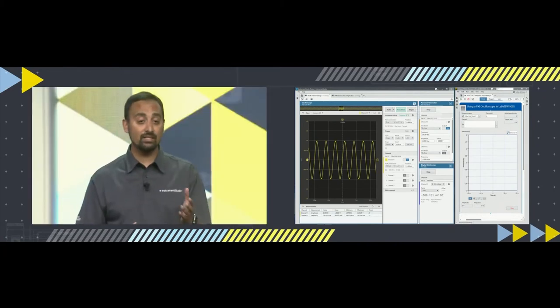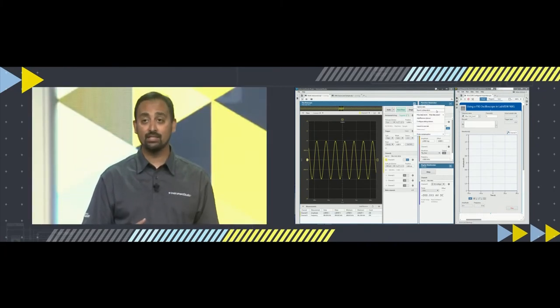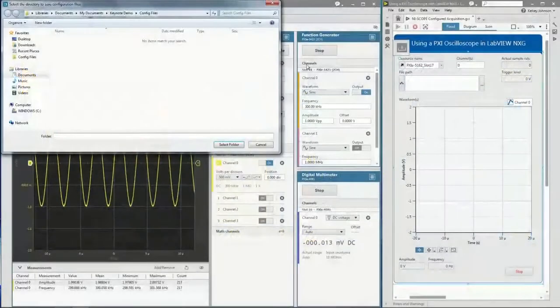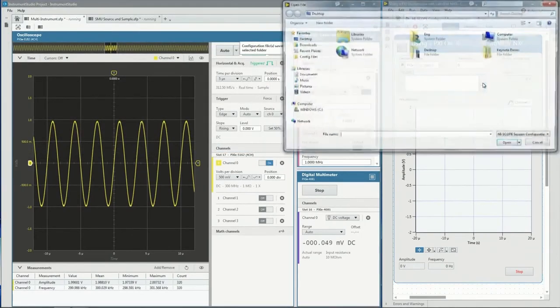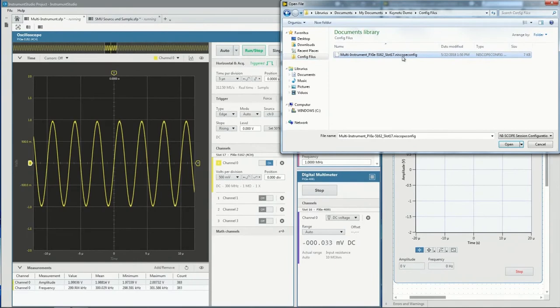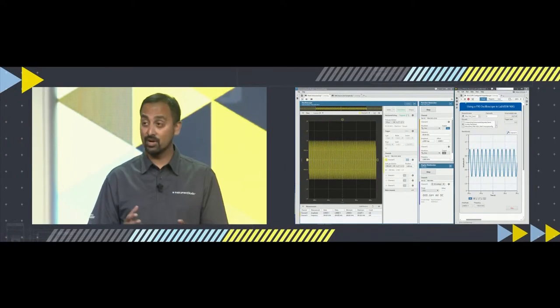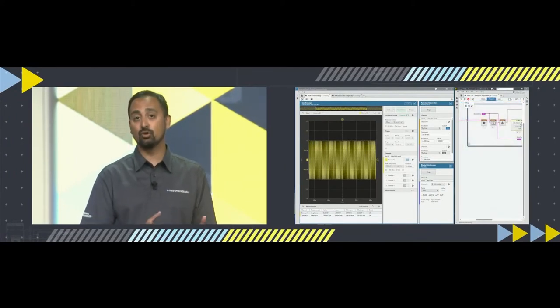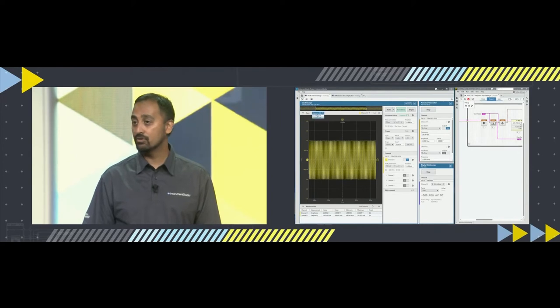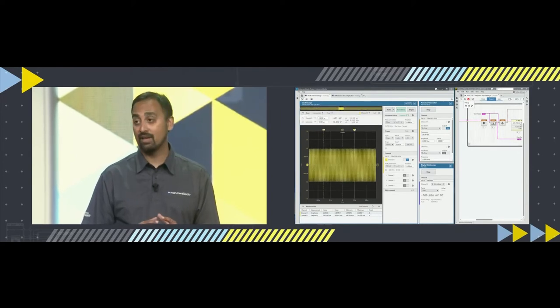That's right. We can easily reproduce our interactive setup by exporting an oscilloscope configuration file, which includes all the instrument settings, to LabVIEW. This allows users to have confidence that their measurement results and instrument settings will correlate with their automation code. When we run the VI, Instrument Studio takes it to the next level by automatically becoming our debugger and displaying the instrument's current state. At a breakpoint, we can even take control of the instrument, allowing users to more rapidly debug their code without having to modify it.